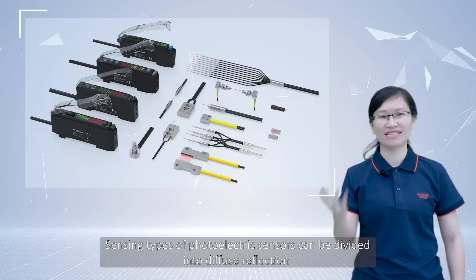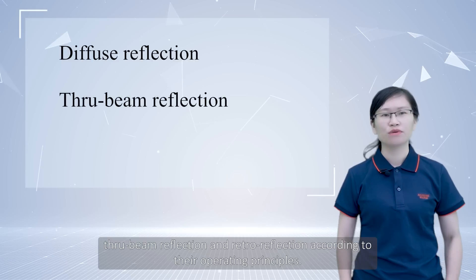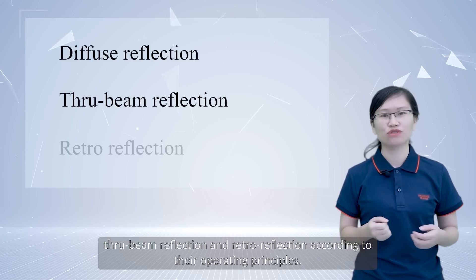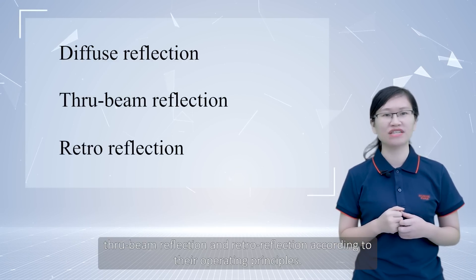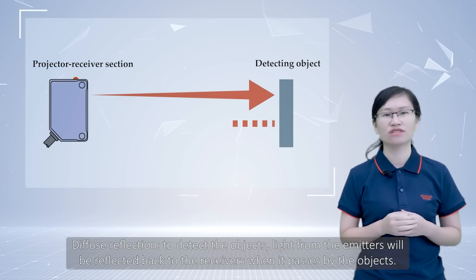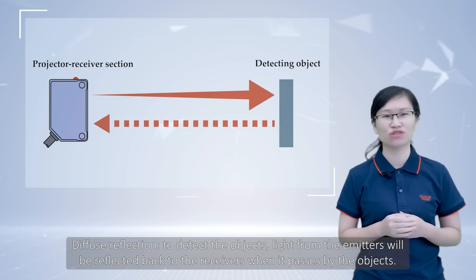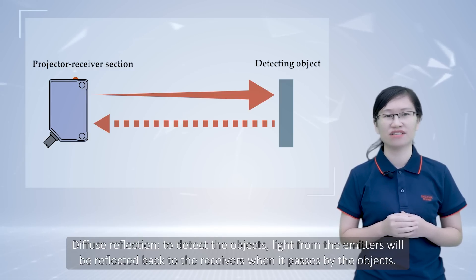Photoelectric sensors can be divided into diffuse reflections, through-beam reflections and retro reflections according to their operation principles. For diffuse reflections, to detect the objects, light from the emitters will be reflected back to the receivers when it passed by the objects.